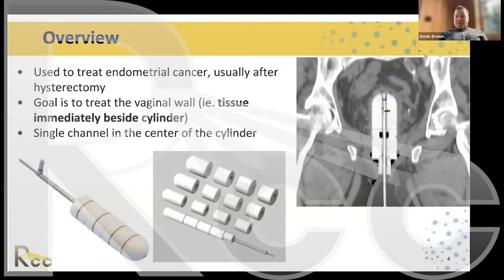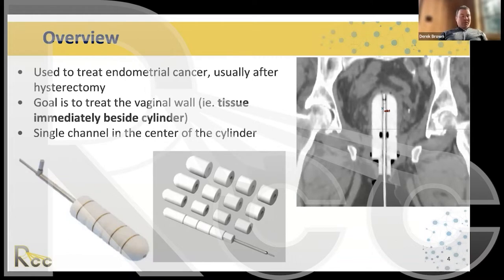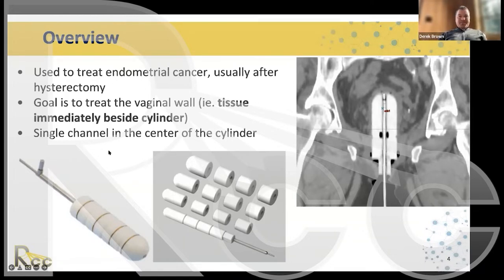The goal is to treat the upper part of the vaginal wall. In terms of channels, we have just one single option — a metal tube running through the center of the cylinder. We run the source through the cylinder and stop at various locations; the length of time we stop at each position determines what the dose distribution looks like for that specific patient.